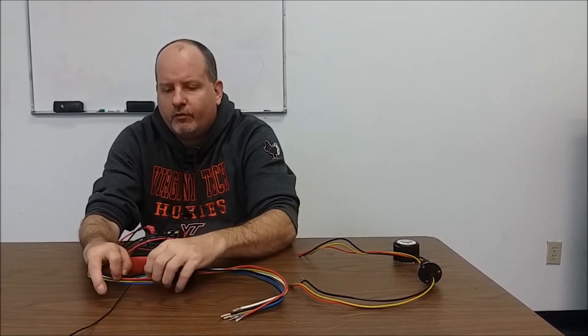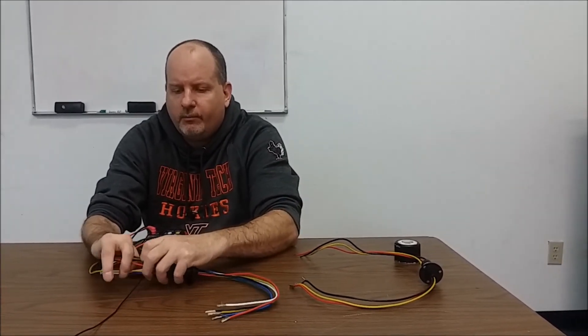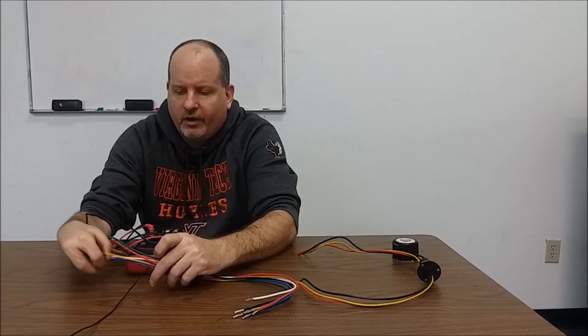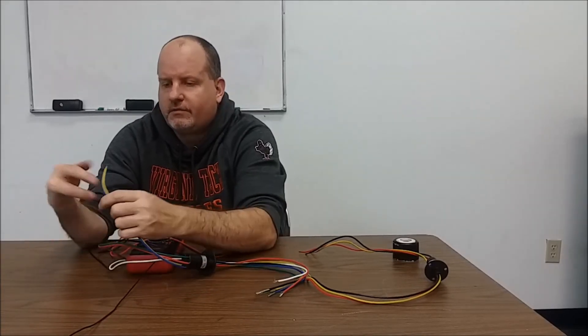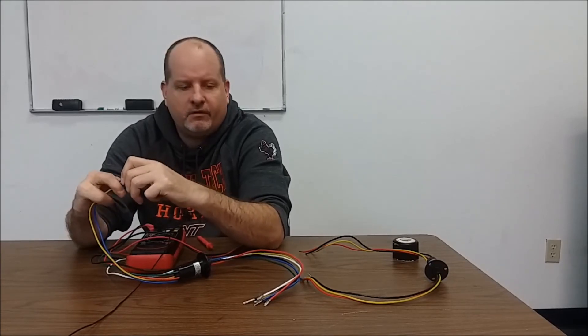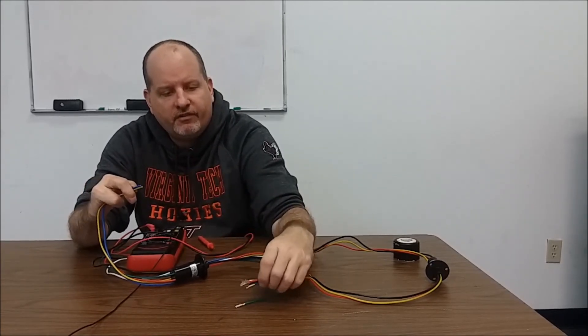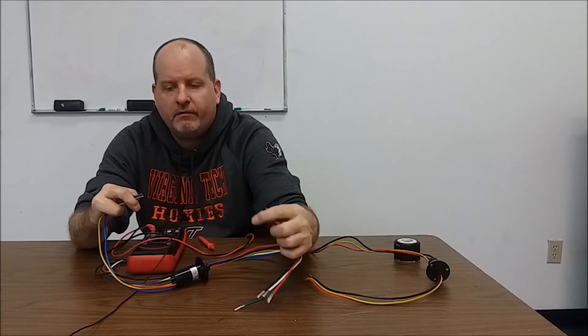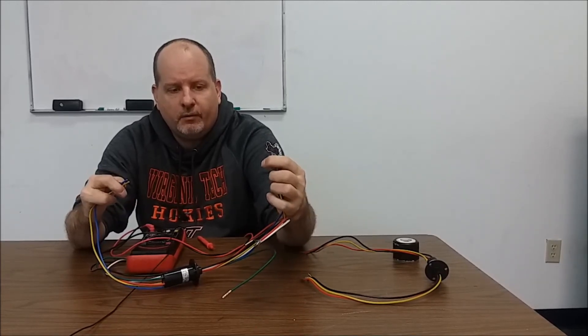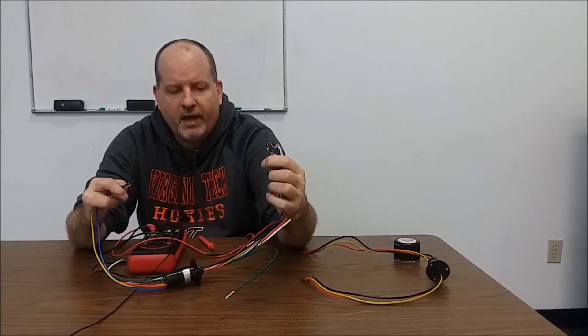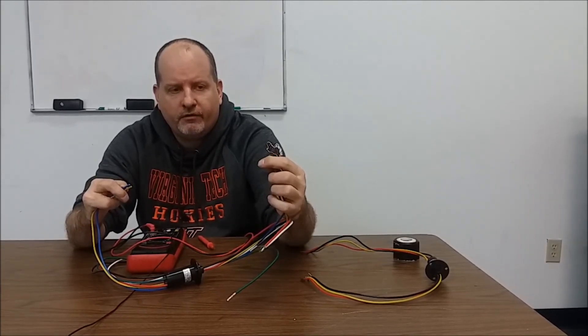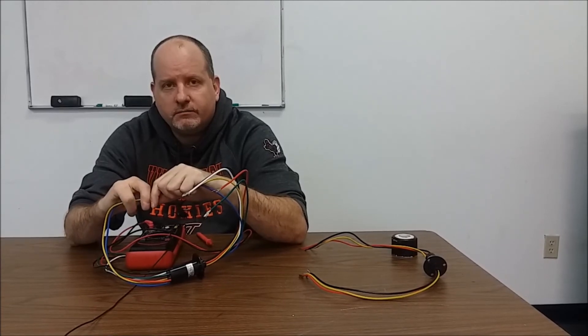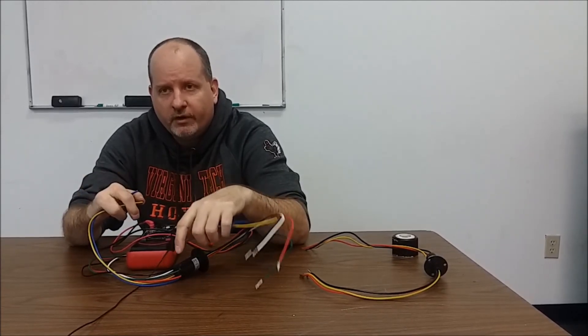What I recommend doing when we're pulling 60 amps is we might take green and yellow, whatever color code makes sense to you, it's fine. We would put these in parallel. Same thing on the other side, take your blue and yellow, put them together parallel. Then maybe we would take the green and white and the red and black and put those in pairs. We would run each phase in parallel.